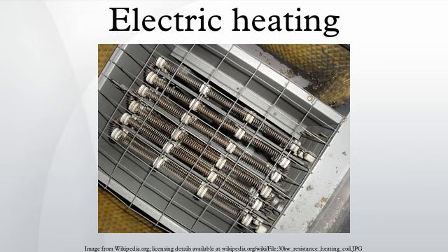In a typical off-peak installation, a lower immersion heater is connected to the separately switched off-peak heating circuit and an upper heater is connected to the normal circuit via its own switch. The consumer then has the option to top up the available hot water supply at any time, rather than waiting for the cheaper supply to turn on. A poorly insulated hot water cylinder will increase running costs because a consumer must pay for electricity used to generate lost heat. Electric shower and tankless heaters also use an immersion heater that is turned on with the flow of water. A group of separate heaters can be switched in order to offer different heating levels.